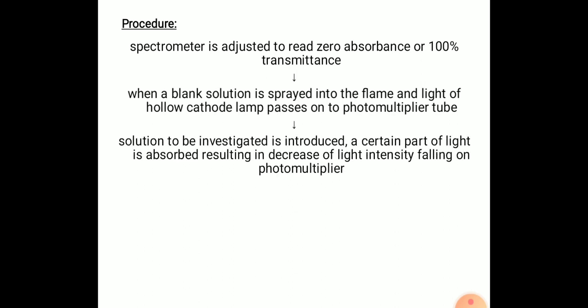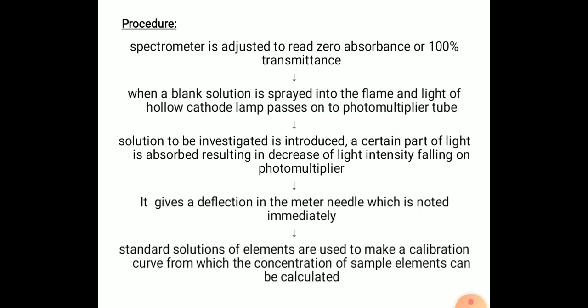Next, the solution to be tested is introduced and a certain part of light is absorbed. As the principle says, some of light is absorbed here and that results in decrease of light intensity which falls on photomultiplier. This gives a deflection in the meter needle which is noted immediately. As this is a comparative method, standard solutions of elements are used to make a calibration curve from which the concentration of sample elements can be calculated.